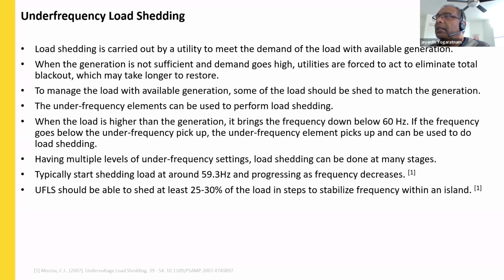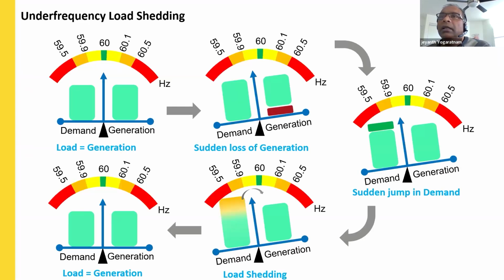When the load is higher than the generation, it brings the frequency down below 60 hertz. So the under frequency element can be set up in such a manner to pick up on an under frequency value, operate an output contact, and disconnect the circuits from the system. That way, we can reduce the load and try to manage the available generation. And this is the roller coaster way of representing it. It is self-explanatory. When the demand is equal to generation, the frequency stays stable at 60 hertz.